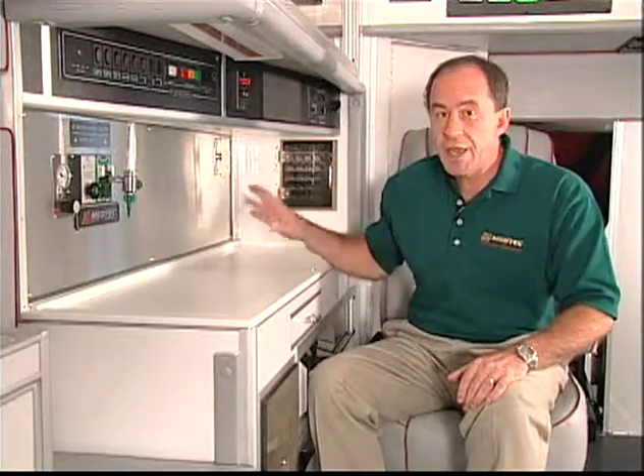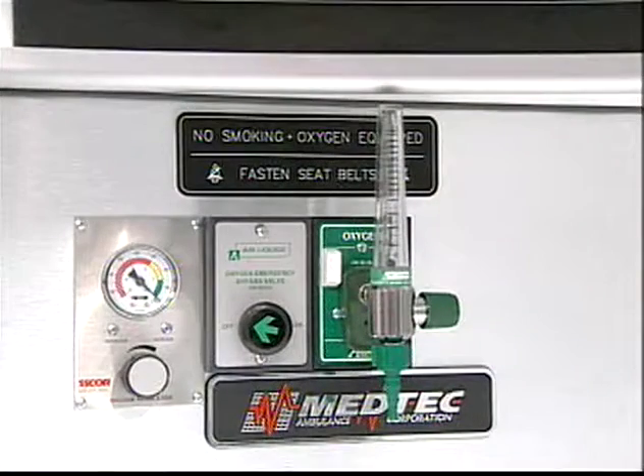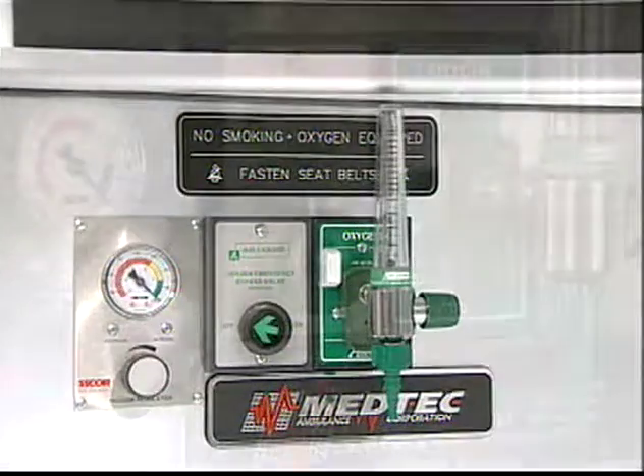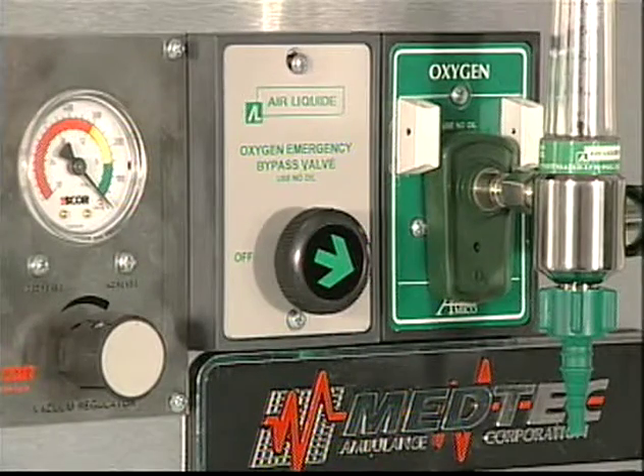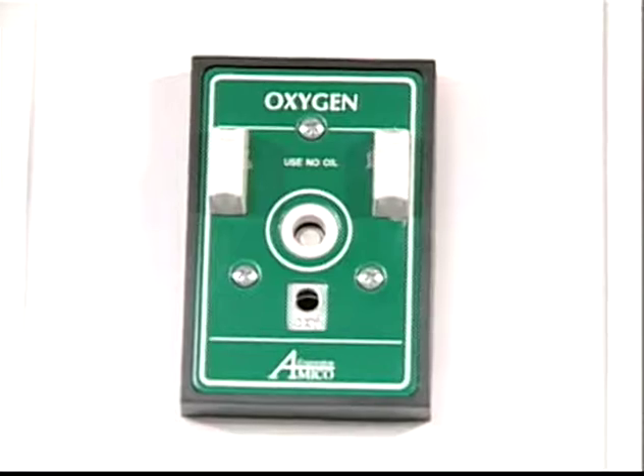If specified, you will have additional oxygen controls located on the main action wall, such as a tank contents gauge or an electronically controlled oxygen valve. Using the oxygen switch located in the rear electrical switch panel provides control of the solenoid-operated oxygen flow valve. This is located in the manual bypass control module located on the main action wall area. When controlling the oxygen flow with the oxygen switch, you must have the manual bypass valve knob in the off position. The manual bypass control module provides you with the ability to manually open and close the oxygen supply valve. The number of oxygen outlets and their location in the conversion is based upon your specification.